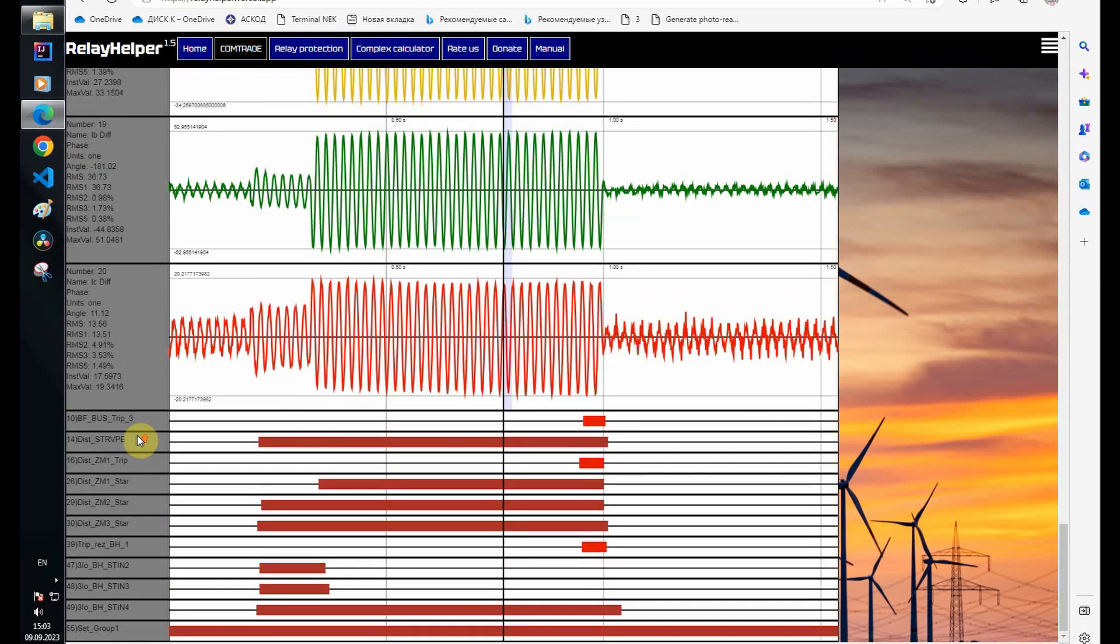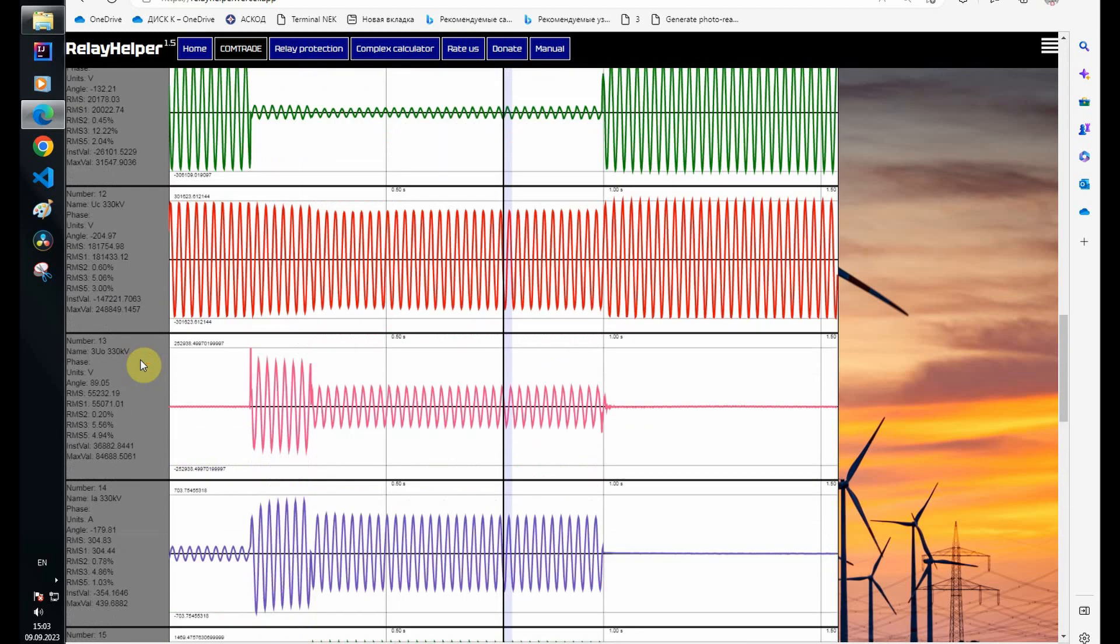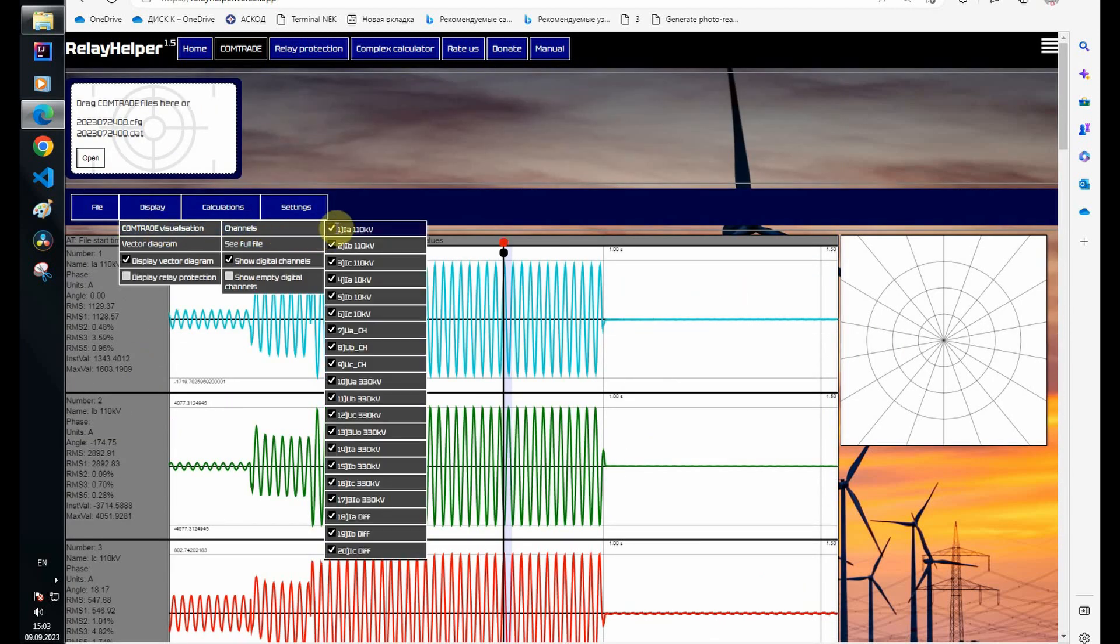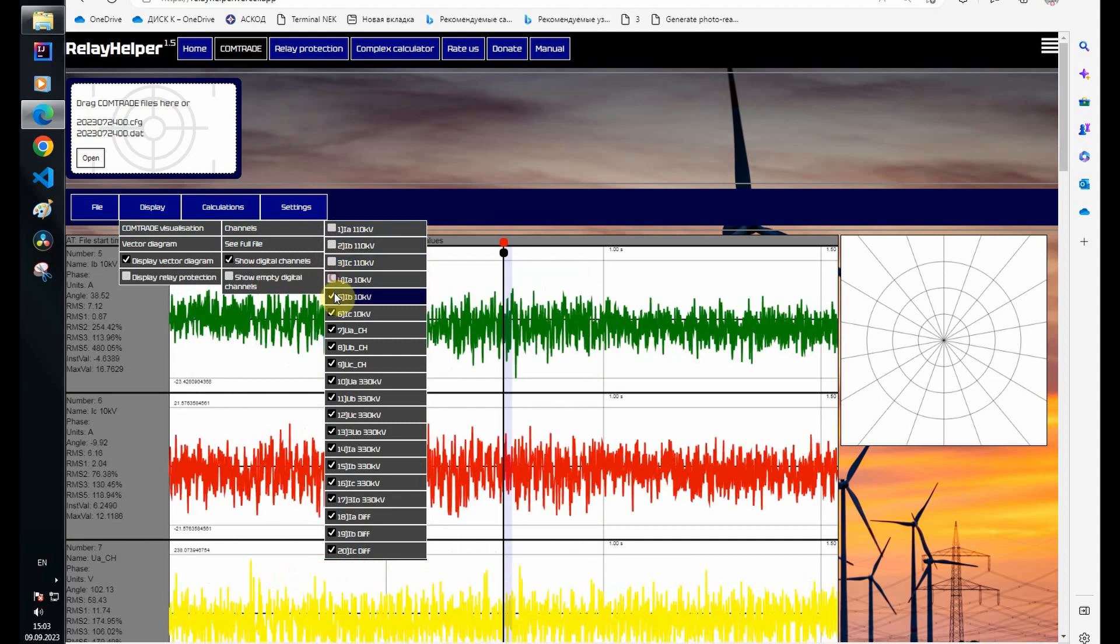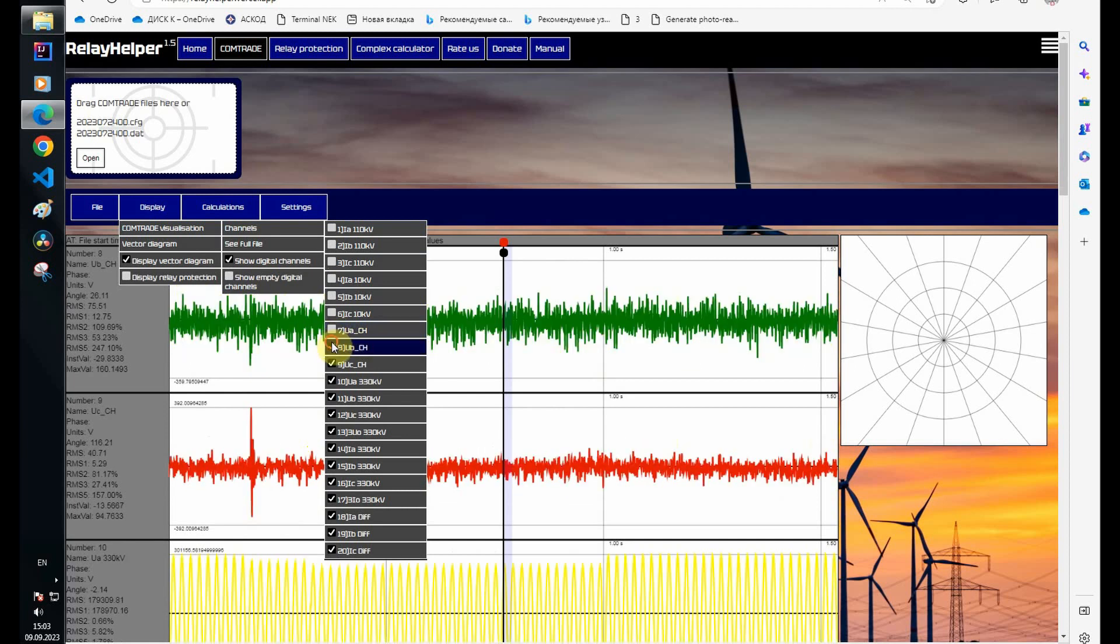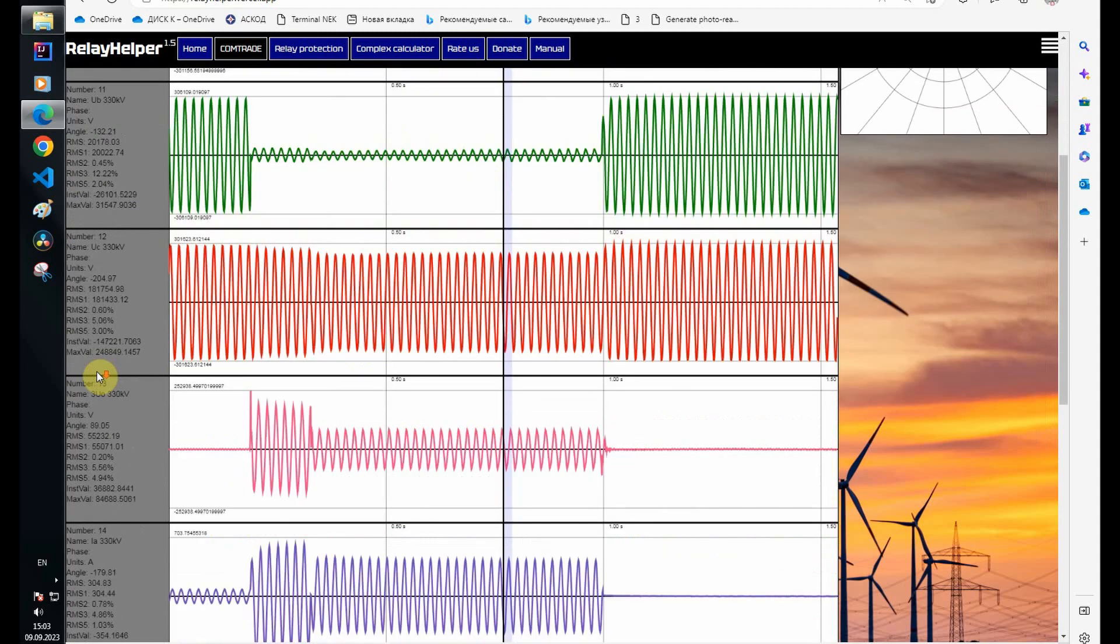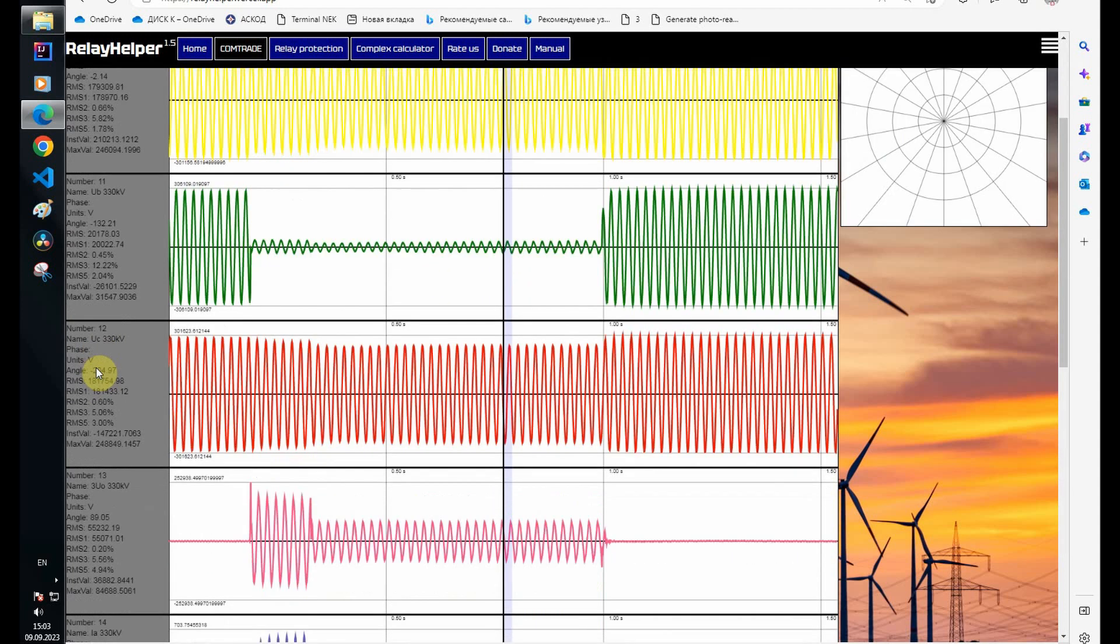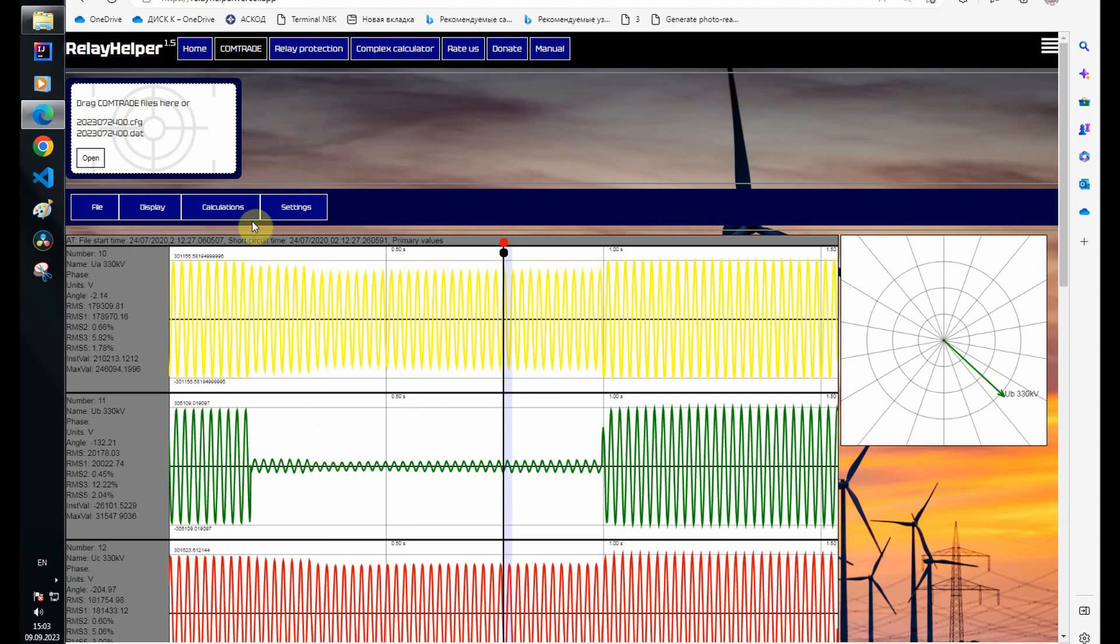I only need 330 kilovolt winding channels. Before starting the analysis, I will look at the direction of the current of this winding. Because the main function of the device is differential protection, the current circuits can be oriented on the recorder for the convenience of its analysis.